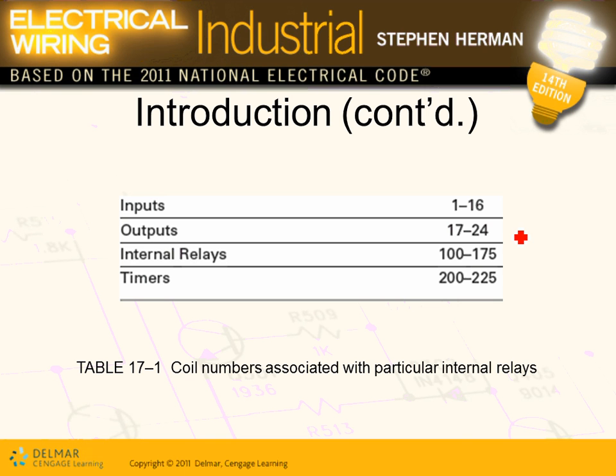When you program PLCs, they give them numbers. Typically 1 through 16 are assigned to the inputs, 17 through 24 are assigned to the outputs. Internal relays start from 100 all the way to 175, and timers are assigned 200 to 225. They don't overlap — as far as the PLC is concerned, it doesn't distinguish, so you have to assign them separate unique numbers.